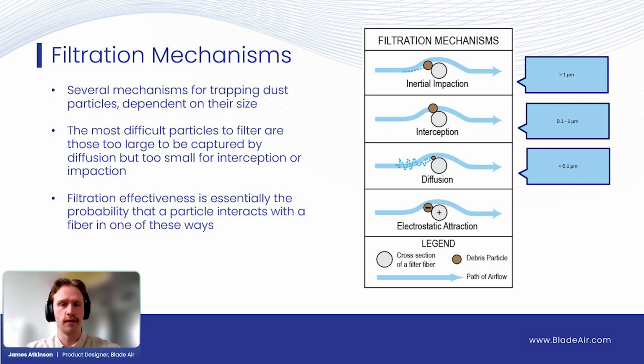Moving down to the next size is inertial impaction. Basically, this happens when a dust particle is too large to follow the air path. Within a filter pad or air filtration media, you have many small air paths winding through the media. Larger particles have too much inertia and can't follow that path. So they smack into a filter fiber, lose their momentum, and are trapped either by gravity or just get stuck in the filter. Moving down to around 0.1 to 1 microns, you have interception. It's very similar, but this is when the particle is small enough to follow the airstream, but it still has some inertia, so it physically touches one of the filter fibers and is trapped just by contact.